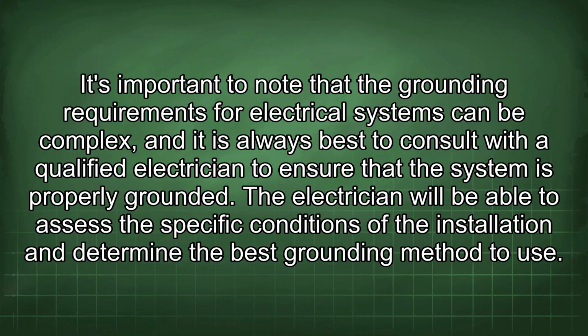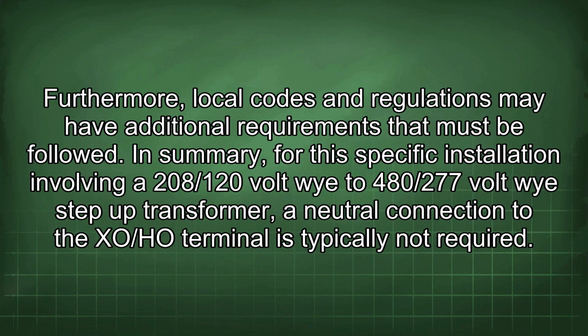The electrician will be able to assess the specific conditions of the installation and determine the best grounding method to use. Furthermore, local codes and regulations may have additional requirements that must be followed. In summary, for this specific installation involving a 208/120 volt Y to 480/277 volt Y step-up transformer, a neutral connection to the XO/HO terminal is typically not required.